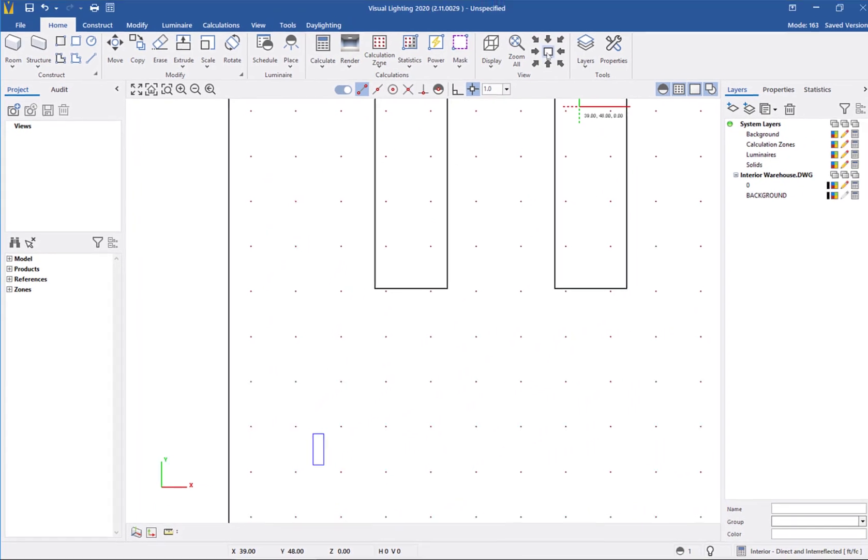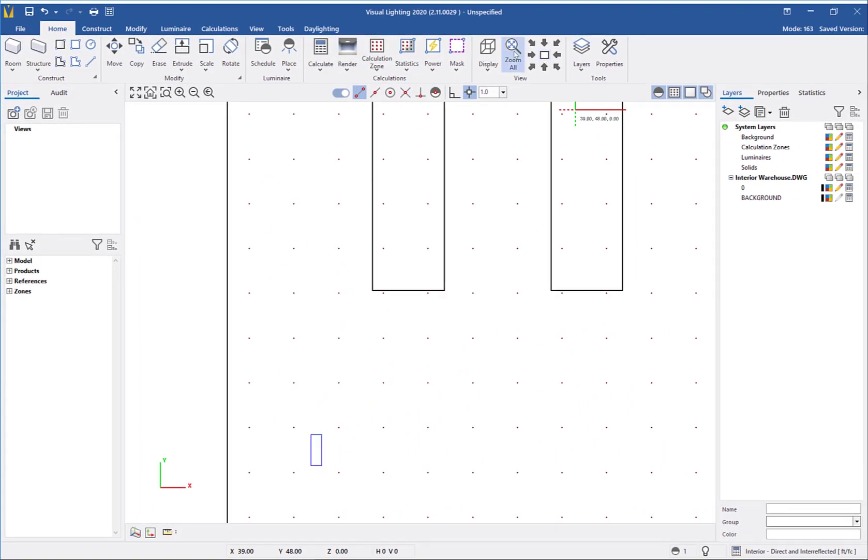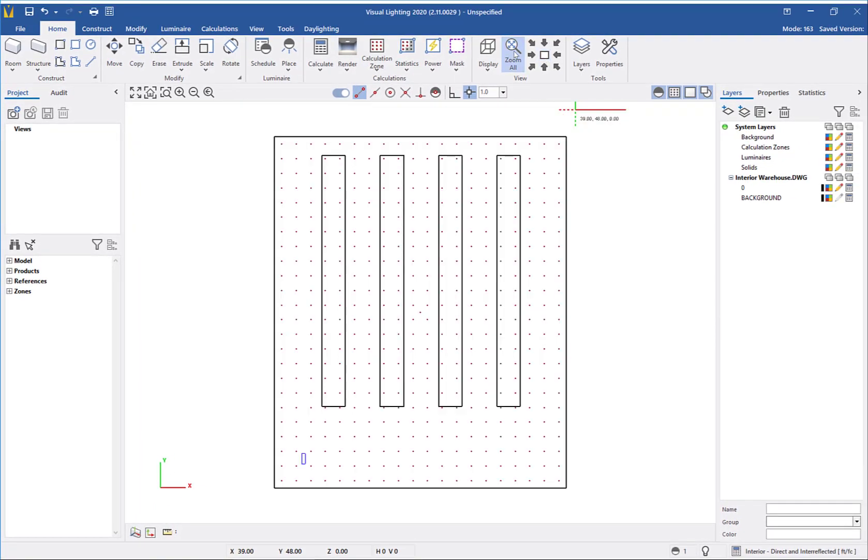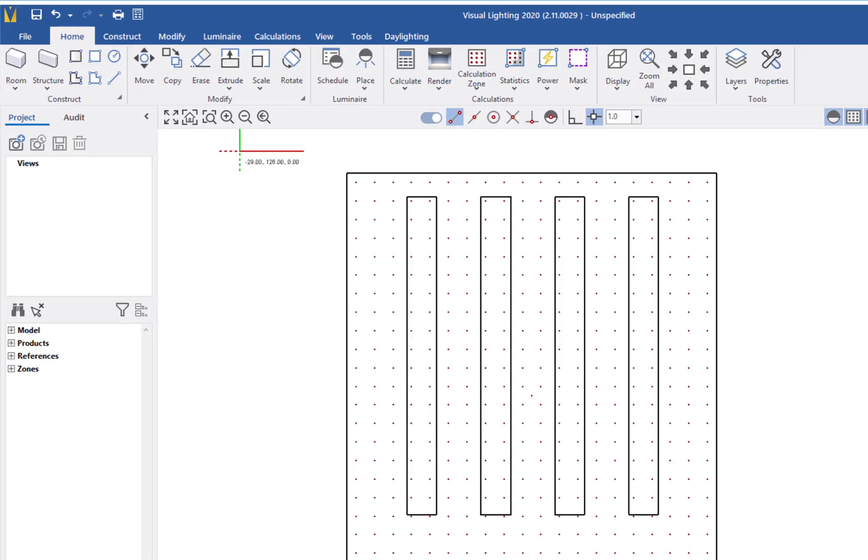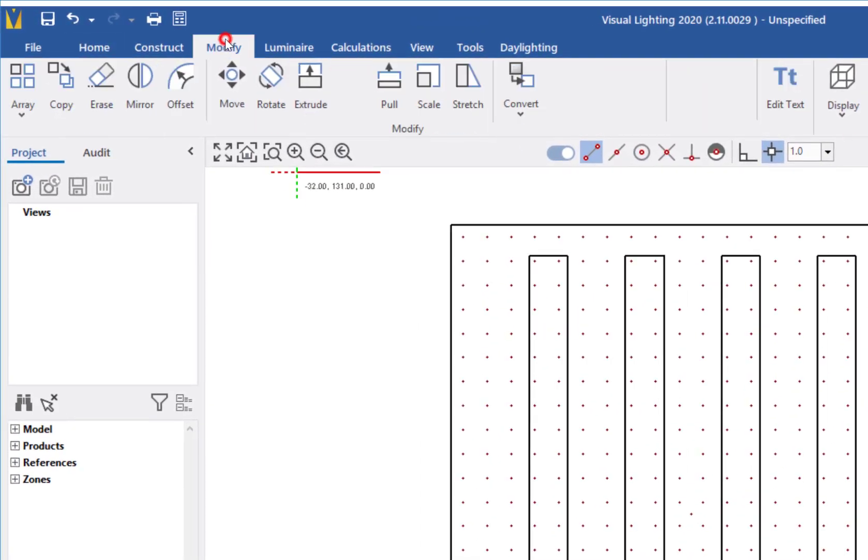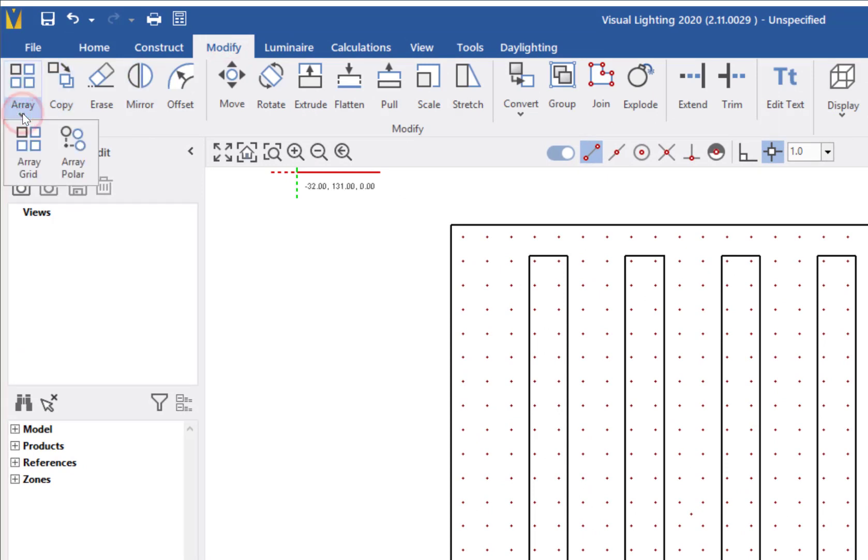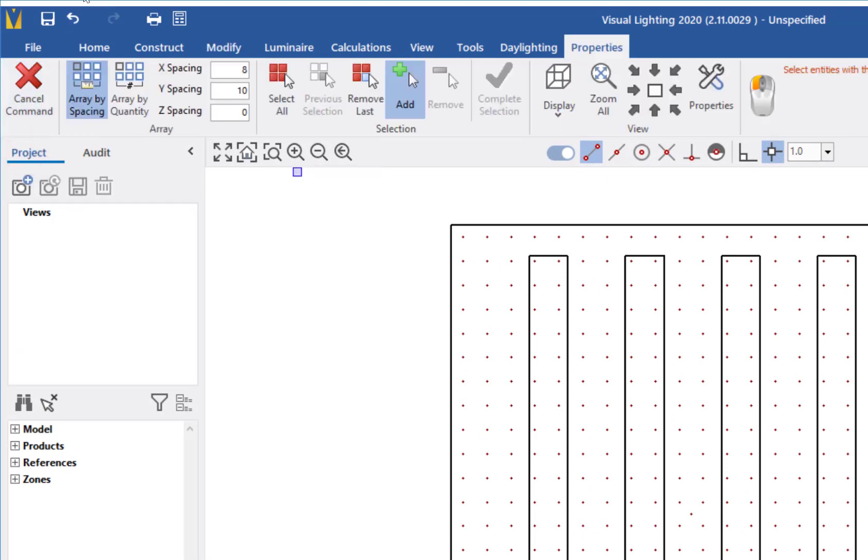Instead of manually placing all luminaires, I will use the array command and insert the rest of the luminaires at a set spacing from the first luminaire. From the modify tab, select the array grid button, and then select array by spacing. I will change the x and y spacing to 20 feet.